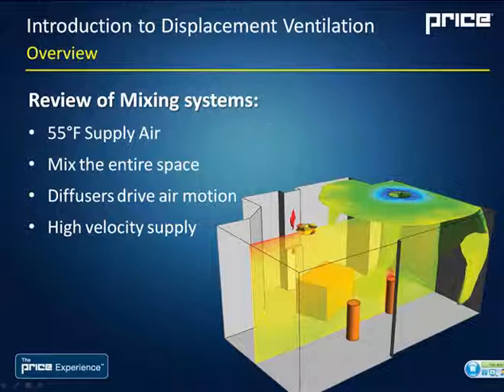Now what you're getting here is the diffuser is driving the air motion. So we're having diffuser exit velocity of a few 100 feet per minute at least, up to 1,000 feet per minute. Very high velocity and very rapid mixing. We're mixing up that room entirely.